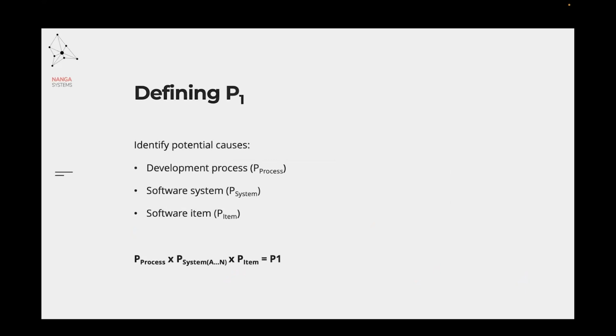And software risk management is all about how we reduce the likelihood of software to contribute to a hazardous situation. This is all about reducing P1. P2 is about reducing the likelihood of harm occurring. Risk controls reducing P2 are likely to be outside of the software and should be documented in system risk analysis. The right mindset when we start working with software risk management is that the software failure always occurs. The reason behind this is that it is almost impossible to estimate the probability of a software failure.